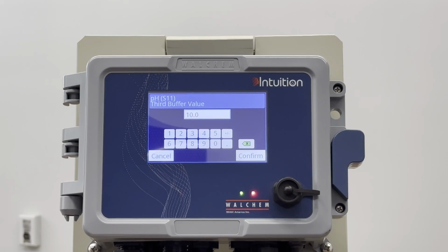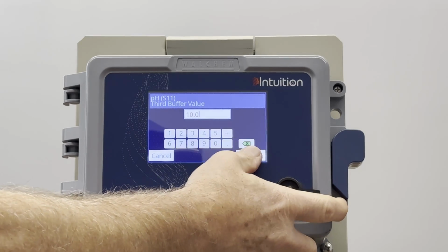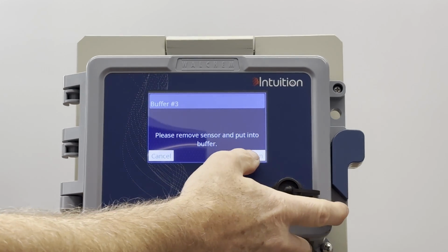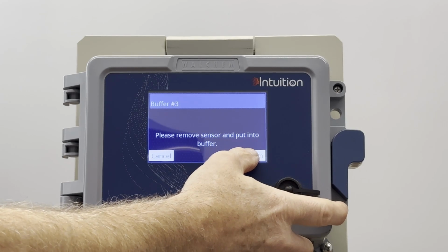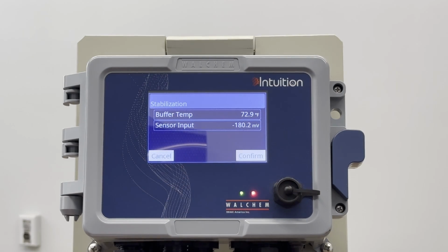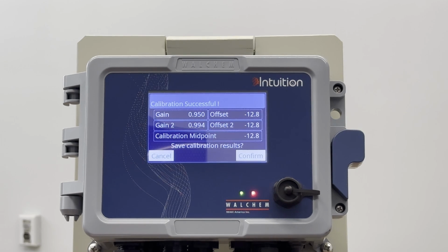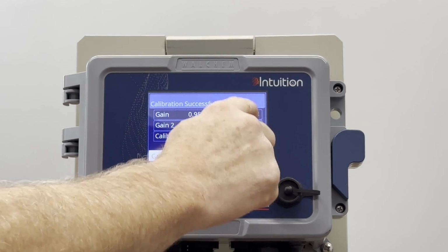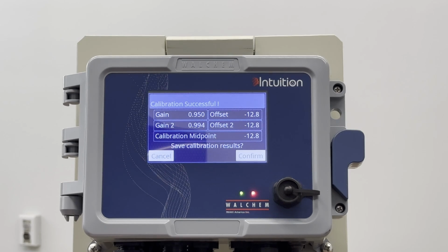I wait for a minute or two. So after I've waited some, I hit confirm. It'll tell me to go ahead and put the sensor in that buffer, which I've already done. I hit confirm, and it'll stabilize and it'll get a value. Now after it does this 3 points, you'll get 2 gains and 1 offset. You see all the offsets are the same.